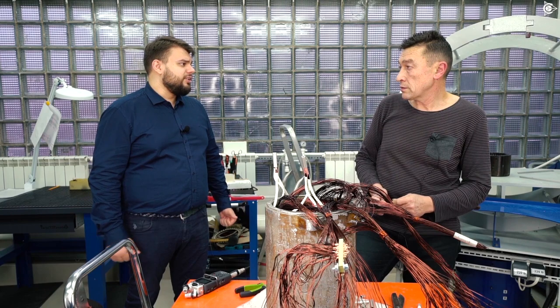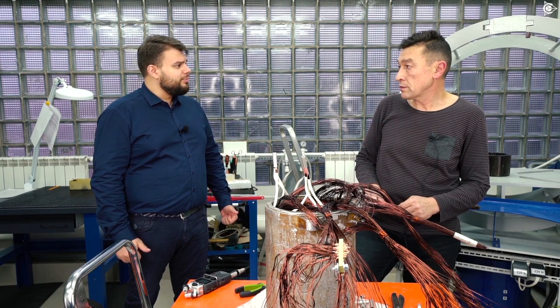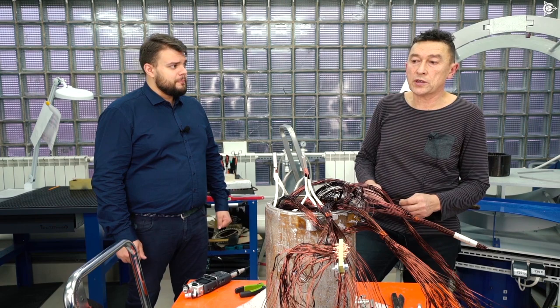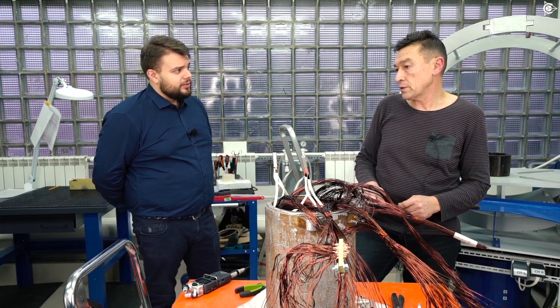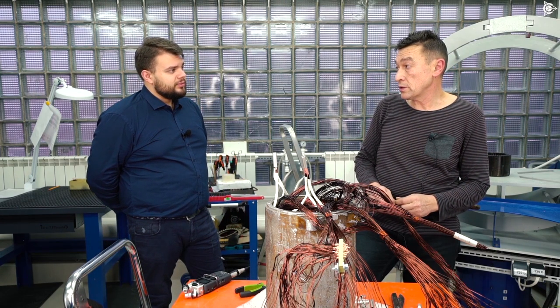I suppose Dmitry Alexandrovich said this was a matter of about 3 months, if I'm not mistaken. That's right, because we equipped the first 55 kilowatt motor with a meter. We put a meter on it before winding, then disconnected and rewound it. It took exactly 3 months to pay off, and it's a 55 kilowatt motor that works non-stop, day and night. He gave it 3 months to pay off. Yes, it's true, and this person is still here.